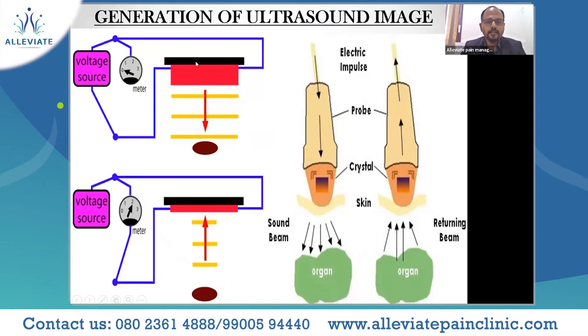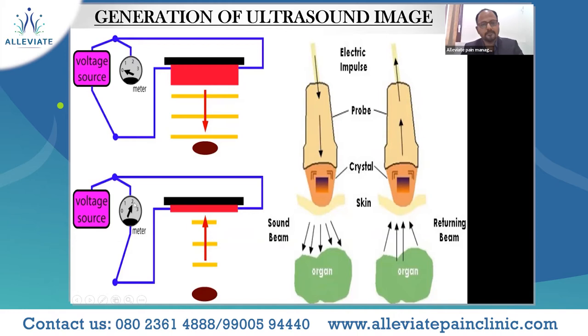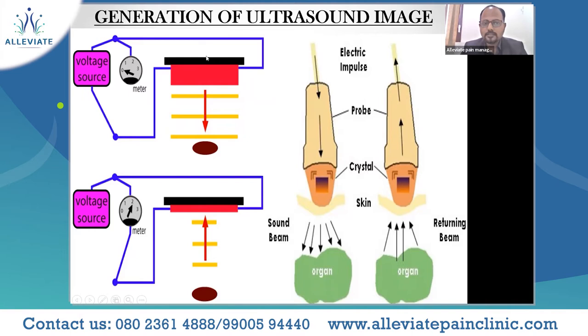Looking at the array of piezoelectric crystals: there are two processes — production of the wave and reflection of the wave. During reception, the voltage meter detects an electrical current. The reflected sound waves — the mechanical stress on these piezoelectric crystals — generate a current. That is the piezoelectric effect. So initially it starts off as the reverse piezoelectric effect, and then becomes the piezoelectric effect to finally produce the image.